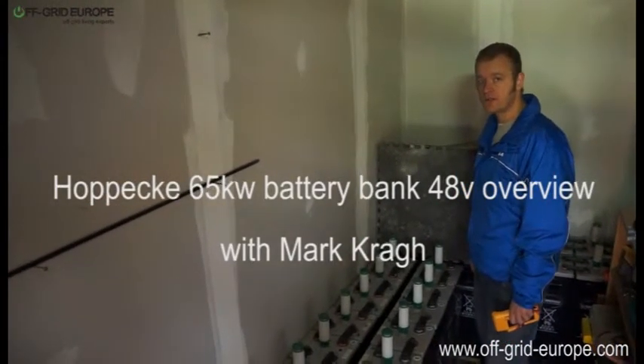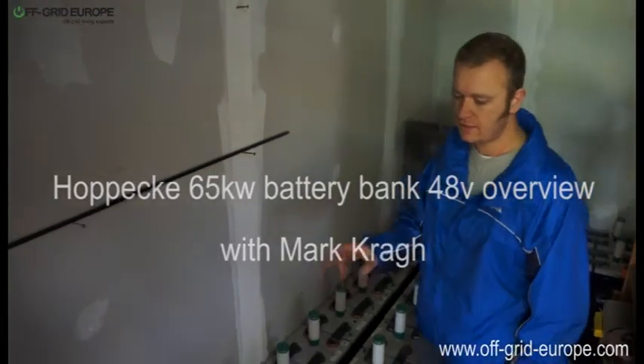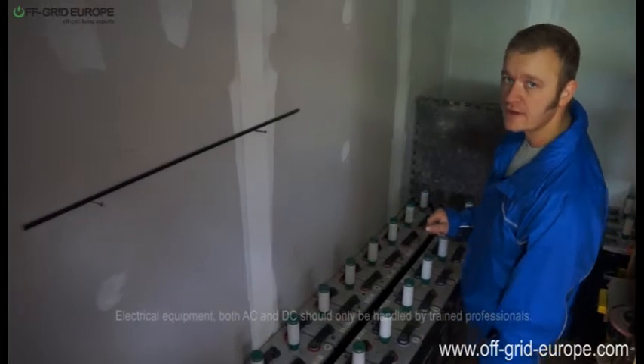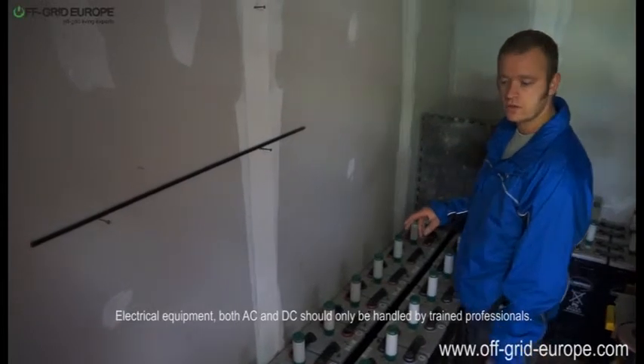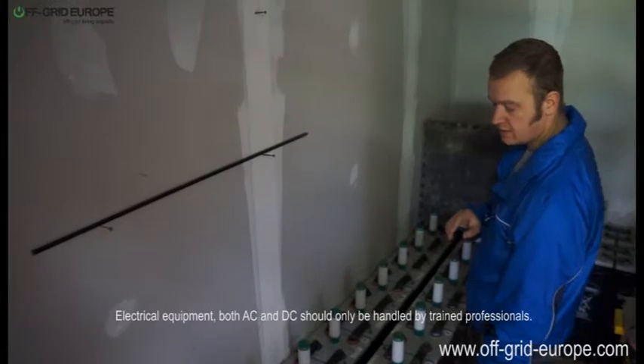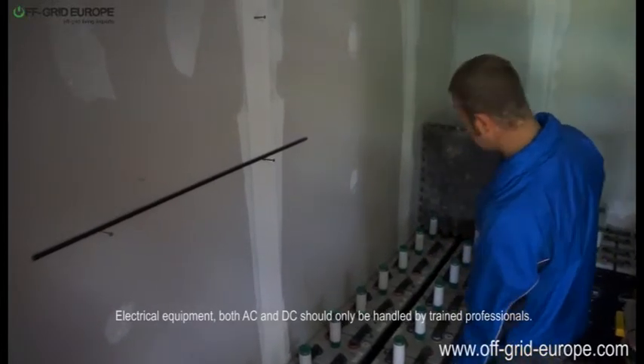Hello, my name is Mark from Off Grid Europe and this is a 48 volt Hoppecke battery bank. The capacity of this battery bank is around 65 kilowatt hours at C100 and this battery bank was installed about one year ago by us. We commissioned it — we filled up the sulfuric acid into this battery and gave it its first charges.